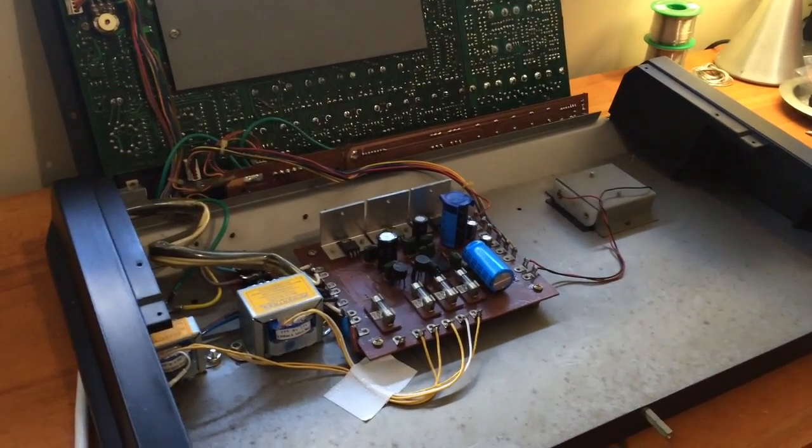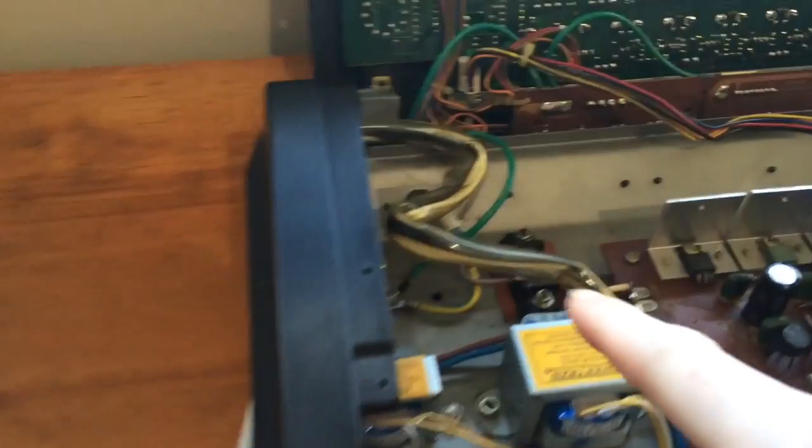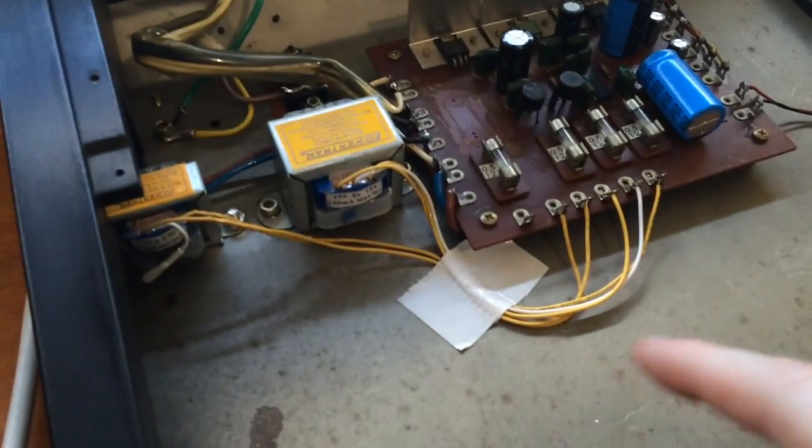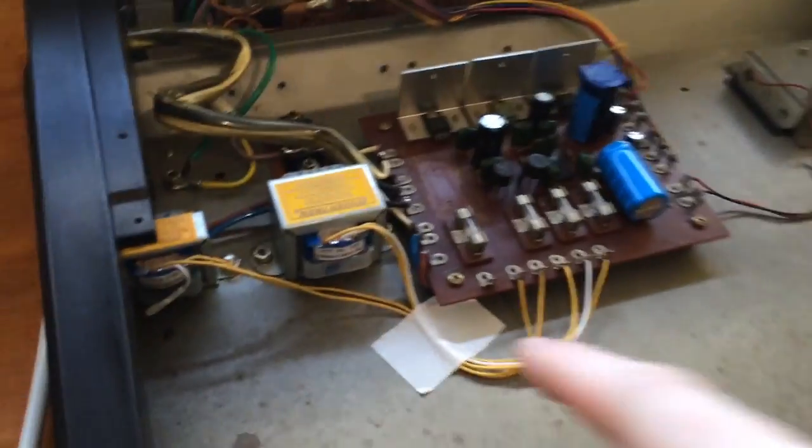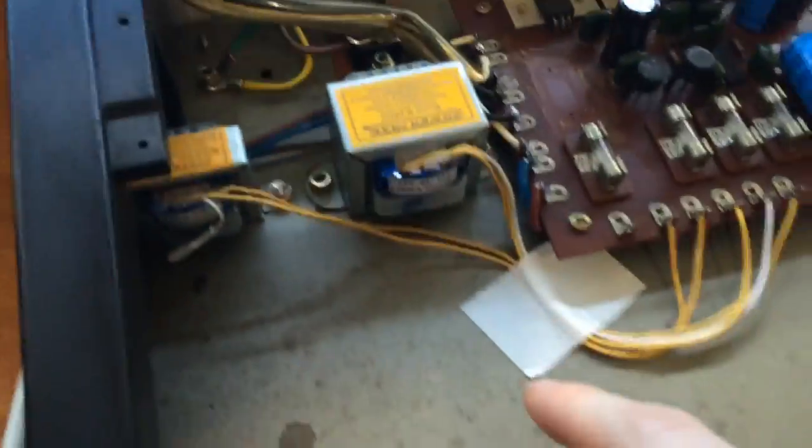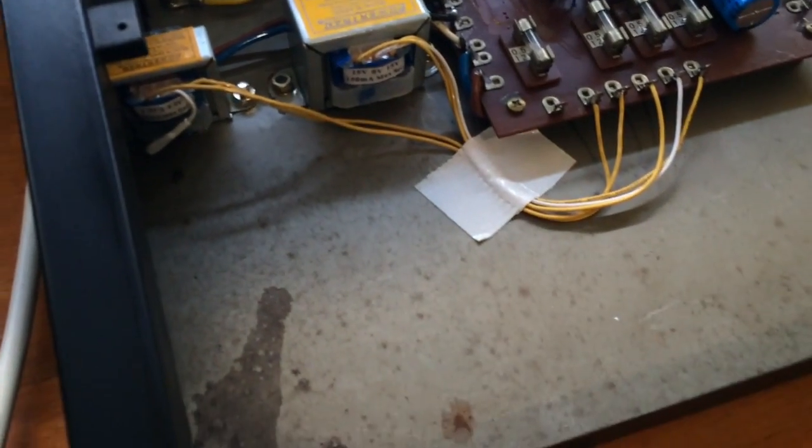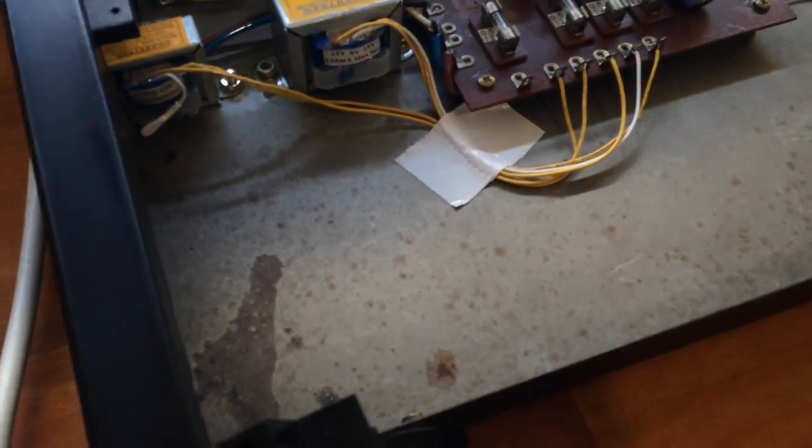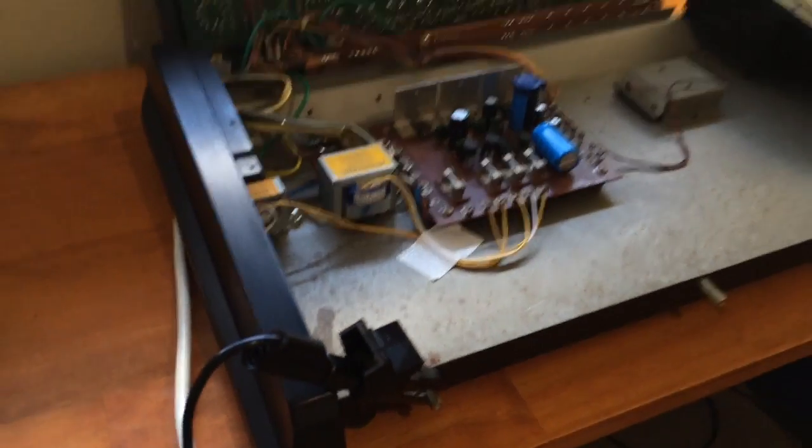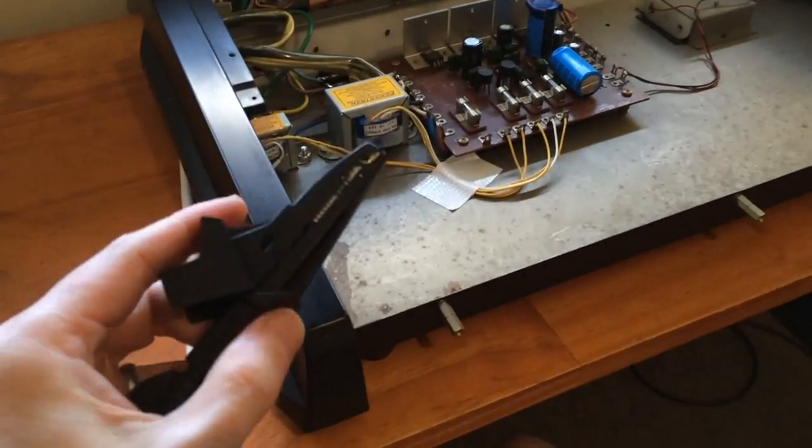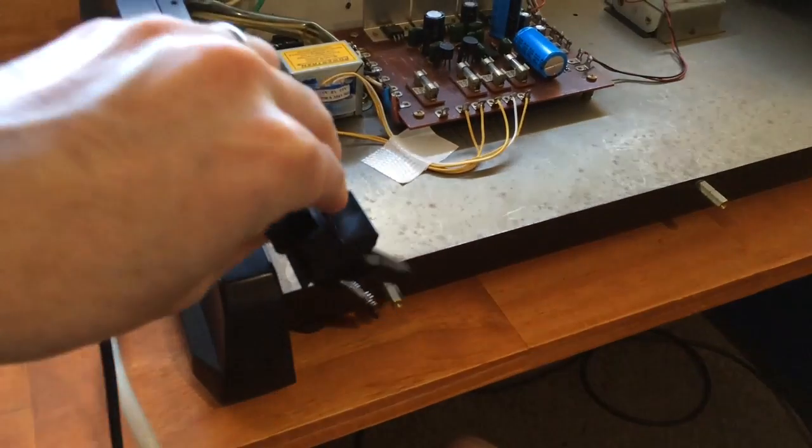But because this has a metal body, if a wire comes loose on the mains and touches the metal, that would be really really dangerous. So we need to test it as a class one device, which means we're also testing for earth in the body.